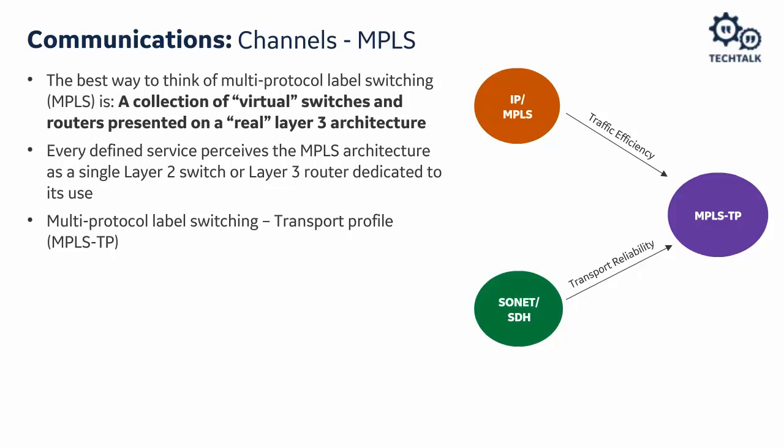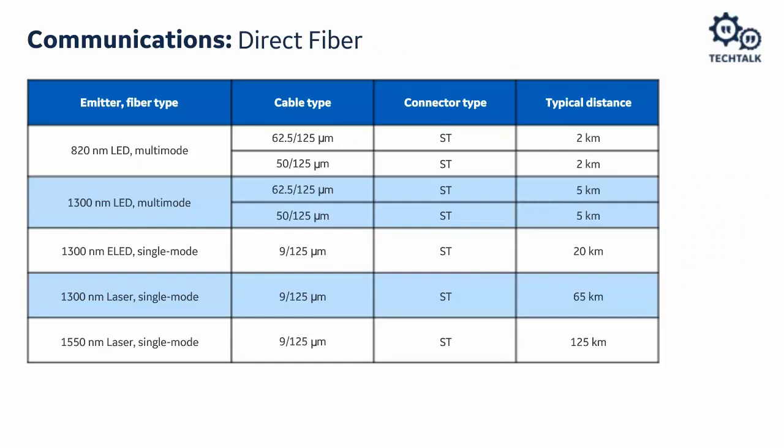This slide gives an idea of how far we can go with direct fiber. Depending on the type of fiber — multimode or single-mode — and the line driver — LED, ELED, or laser — we can go from about two kilometers to 125 kilometers. Direct fiber is still the most preferred channel because it is more secure and doesn't have problems you might expect with a multiplex channel, but unfortunately it is costly.